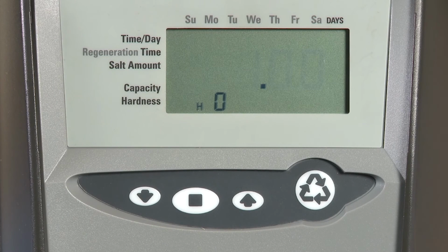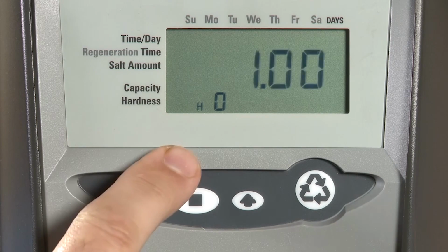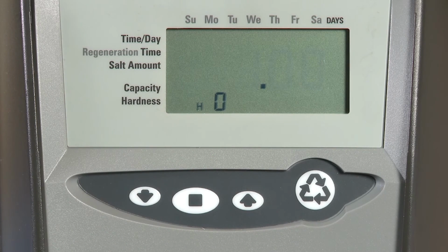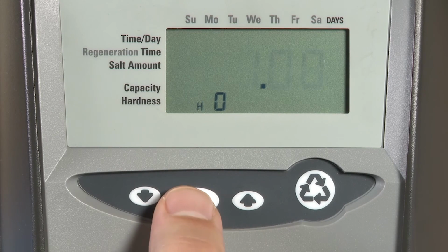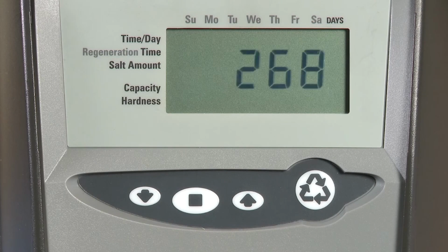If we should need to reset the control, we access the history level by getting to H0. To reset the control, press and hold the set button. When the valve model pops up, the control has been reset.